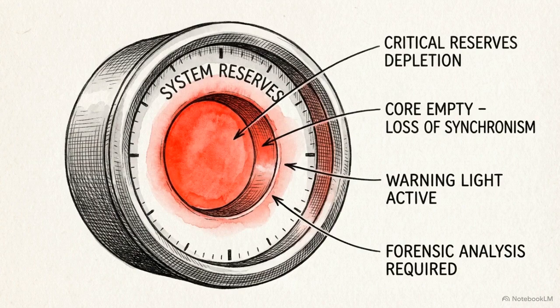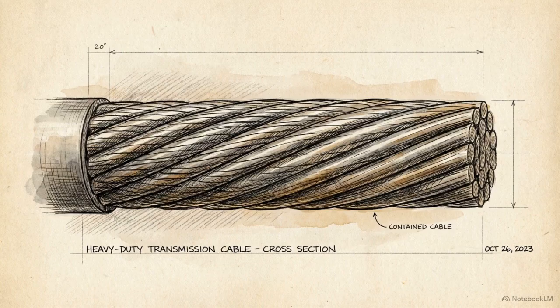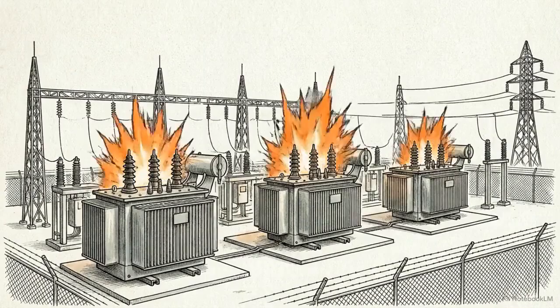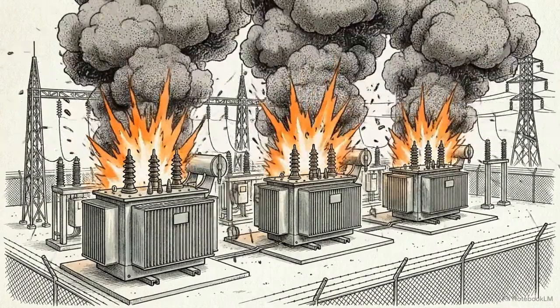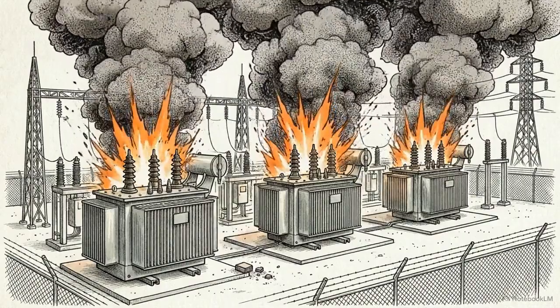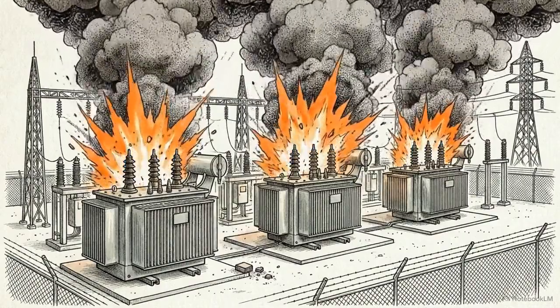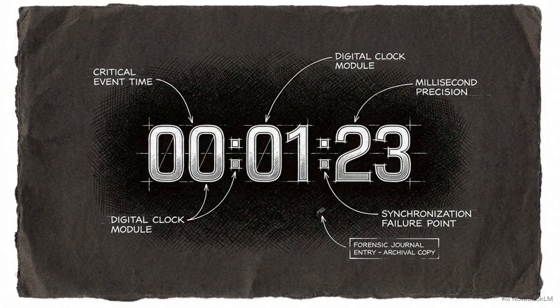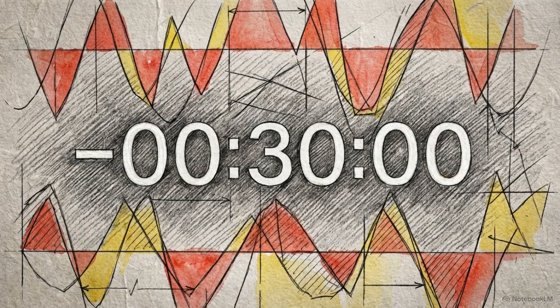Reading from the bottom up, we can trace this failure backward to the specific hardware behaviors and regulatory rules that caused it. The overarching physical mechanism at play was a severe deficit in reactive power absorption. Reactive power is the energy that maintains voltage levels within a system. Without the ability to quickly absorb this excess reactive power, the grid experienced an uncontrollable cascade of overvoltage disconnections. While the final collapse executed in exactly 83 seconds, examining that time frame requires first understanding the highly precarious state of the grid 30 minutes prior to the trigger.